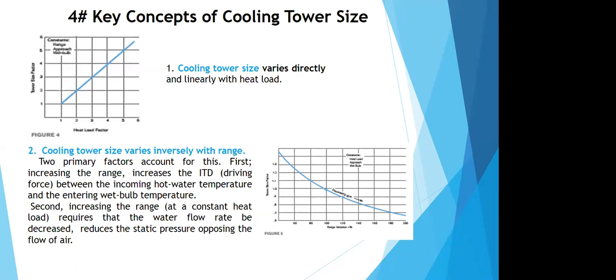So if I have a cooling tower sized with, say, a unit range, and I increase the range, keeping the heat load constant, you can see that the tower size will come down. If I increase the range by, say, 20%, the tower size comes down by almost 10%, and vice versa. If I reduce the range by, say, 20%, my tower size goes up by almost 10%. So if you keep the heat load constant and you simply increase the range of your tower and reduce the flow rate or the mass flow of water, you can reduce your tower size.